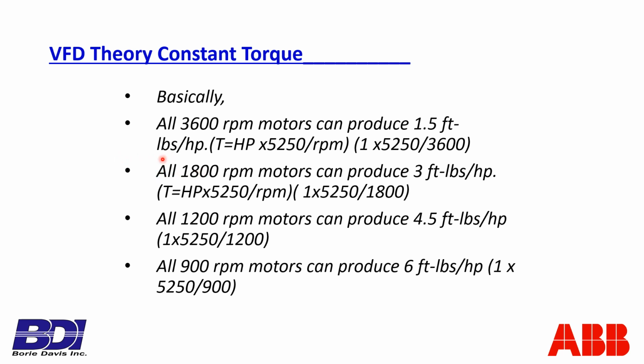Now an 1800 RPM motor, you look at that, well, it's half the RPM rating of the 3600, but if you plug in the same equation, now our divisor is 1800 RPM, well, that's 3 foot-pounds of torque. You can look at these others and you see that the torque available goes up, and that is occurring because the motor choice base speed RPM is causing that equation to produce more torque for a given horsepower. In each case, per horsepower, there's the torque available based on the base speed RPM of the motor. That's just saying the equation works.